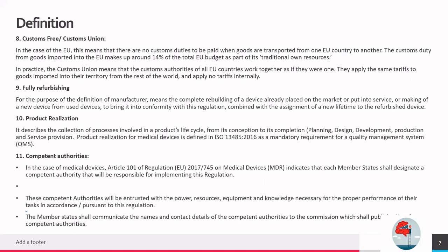Third, transferred from the manufacturer in a third country to an authorized representative in the Union, whom the manufacturer has engaged to ensure that the product complies with the Union harmonization legislation. So, for example, if the manufacturer is in a third country, outside the EU and EFTA countries, and the device is sent to an authorized representative in the Union, whom the manufacturer has engaged to ensure that the product complies with the Union legislation, then they are called indirectly economic operators, right?